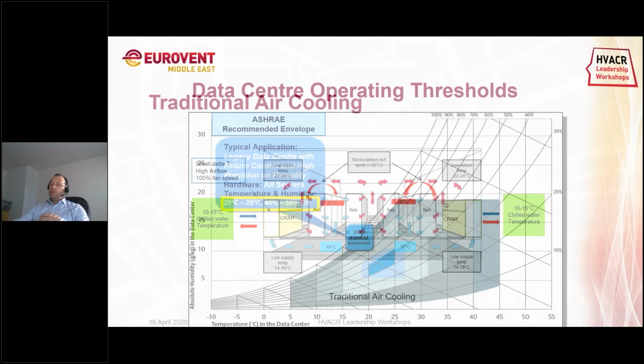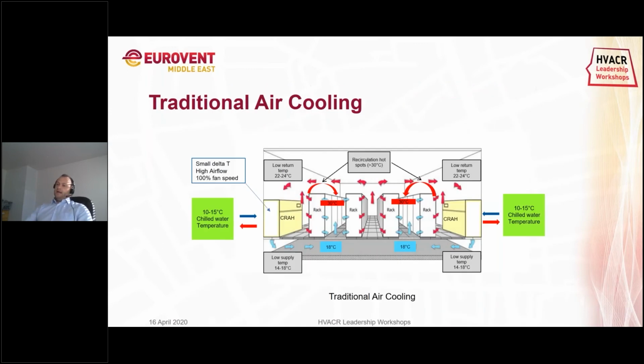To have a better understanding of what was happening initially inside the data center, to give you an idea, this is traditional air cooling, when there is only one room and no separation inside the room. The cold air comes via a raised floor into the servers, and hot air comes out of the server racks. As there is only one room, there is a lot of mixture between the hot and the cold air. At certain points there will be hot spots, but also the cold air will be mixed with the hot air, and the return air will be quite low. So we see here a very low supply temperature and a very low return temperature. Typically, chilled water supply and return temperatures were 10 to 15 degrees. And this was how most of the data centers initially were operating.